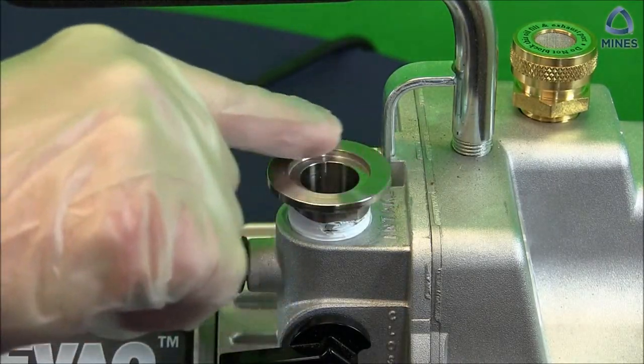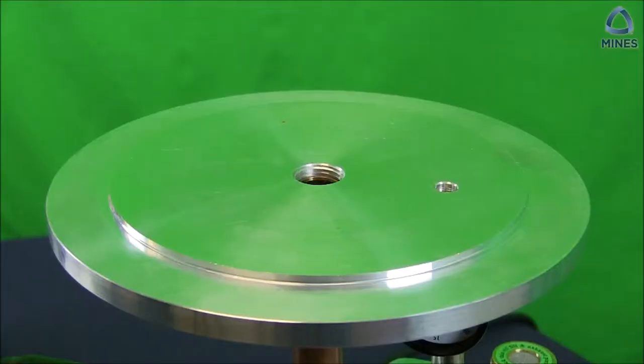Before attaching the aluminum base plate to the pump, it's recommended to put on appropriate gloves to limit the amount of skin oils and dirt that may be deposited onto the vacuum components. Next, visually inspect the sealing surfaces of the flange on both the pump and the base plate.